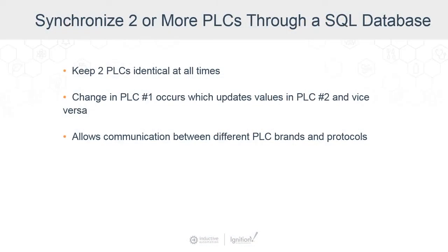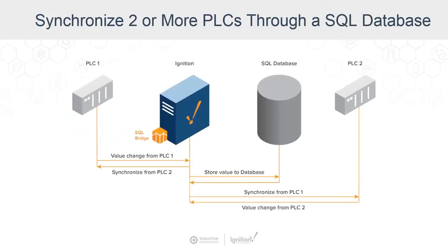Ignition can leverage the power of the SQL database to perform synchronization, and we can have many different PLCs — different brands and protocols. If we need to synchronize a value from one PLC to another, a single Bridge module is perfect for that. If we look at a diagram here, we have PLC 1 and PLC 2; they can be different brands, different parts of the factory, and they're not connected whatsoever, but Ignition can communicate to them individually using drivers.